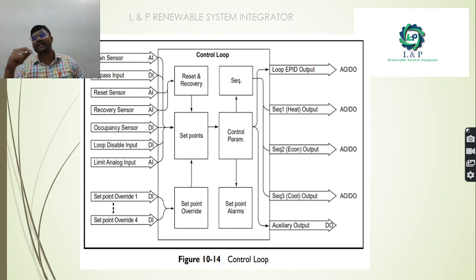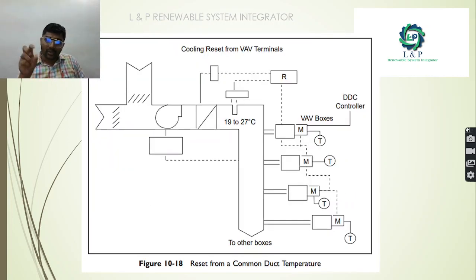Even for the override, as well as any mishappenings that occur outside, you need to raise an alarm. So this is a simple common duct temperature sensor. As you can see here, we have a supply line, we have a supply duct. The temperature is around 27 degrees Celsius. If you want to cool it down, you need the help of cooling valves. We have VAV boxes, and we are controlling the VAV box damper actuators with the help of DDC controllers. For each and every room we have temperature sensors.